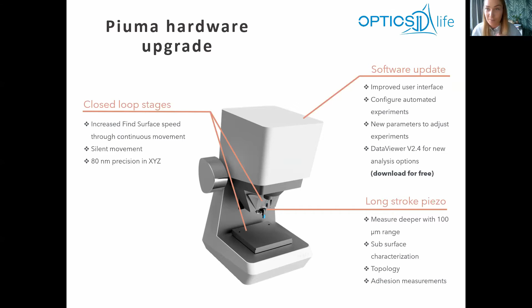The piezo has also changed. Before we had 20 micrometers, now it's 100 micrometers standard, so it's a longer range. That's very useful if you want to sense deeper into the sample. Also, it allows you to work around adhesion, so you have more range to get out when it's sticky. And additionally, you also get the topography information, so you can really get the height profile.